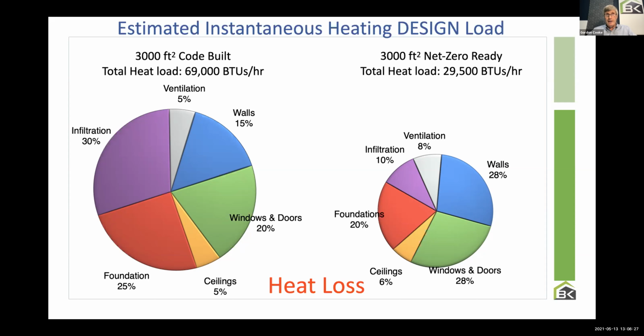When you do a heat loss, the standard algorithms of the day are designed to be worst case. They're not designed to be necessarily accurate. If anything, they want to be a little conservative, a little oversized. And I say that for good reason, because sometimes we hear people say, well, I'm going to do the heat loss and then I'm going to add something to it just in case. No, all the just in case have already been added, and I'll try to show you that's how it works.